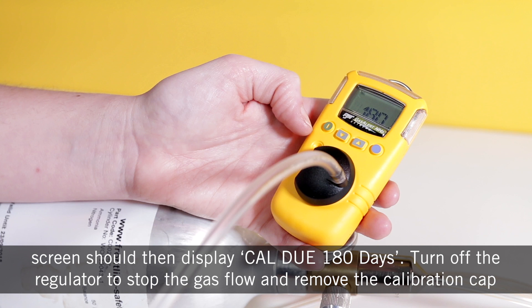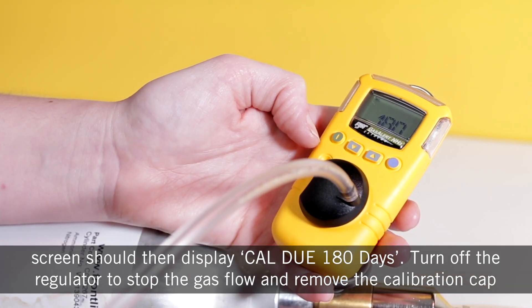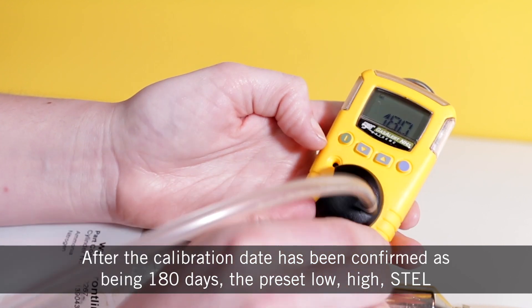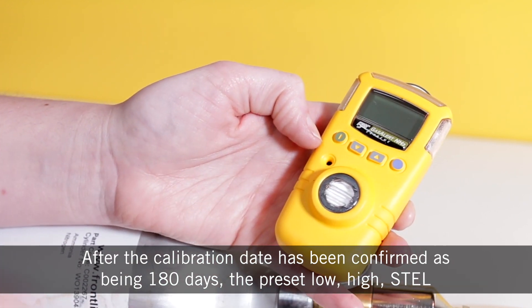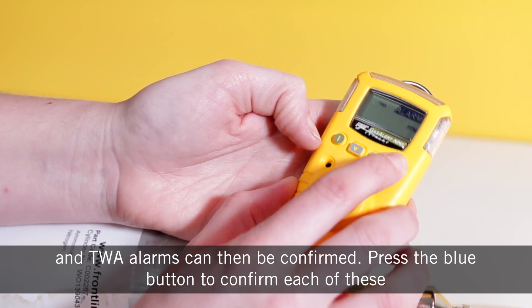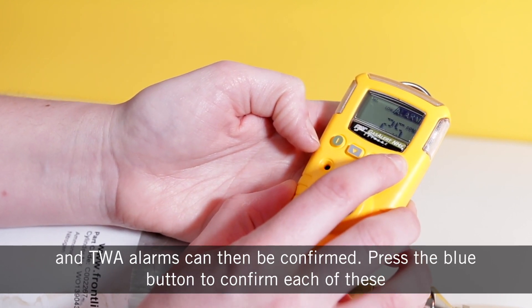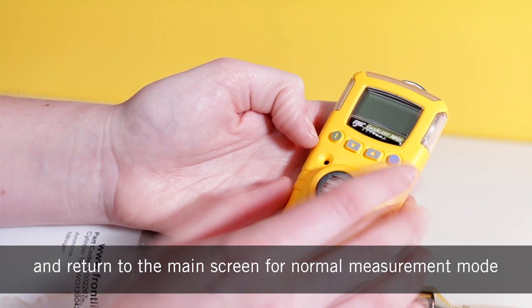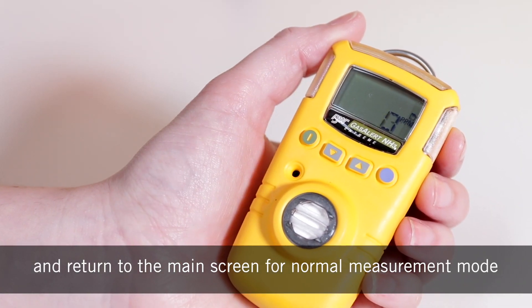Turn off the regulator to stop the gas flow and remove the calibration cap. After the calibration date has been confirmed as being 180 days, the preset low, high, STEL, and TWA alarms can then be confirmed. Press the blue button to confirm each of these and return to the main screen for normal measurement mode.